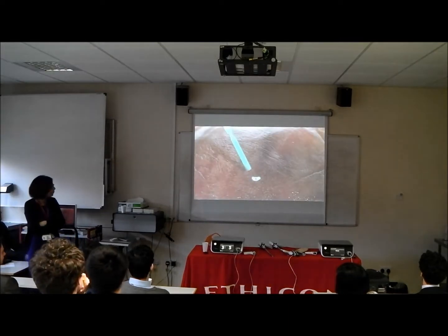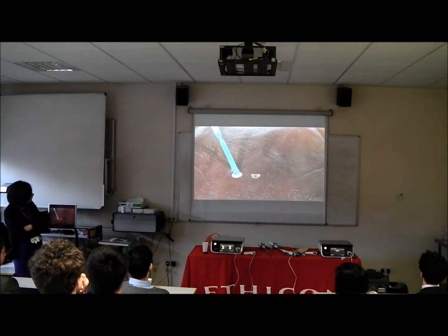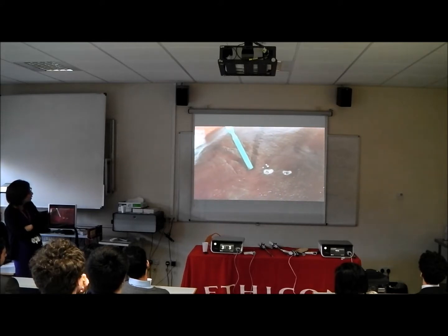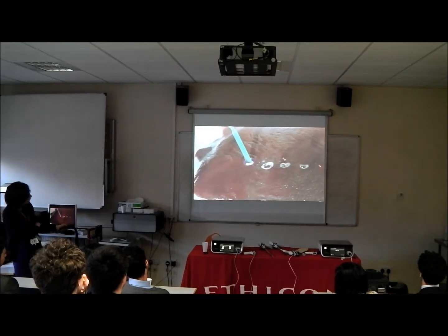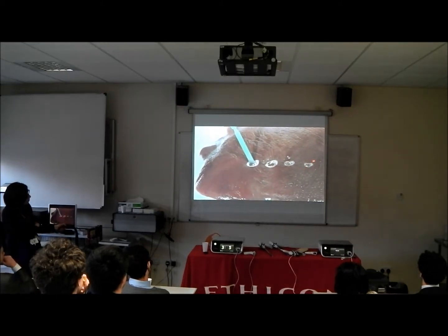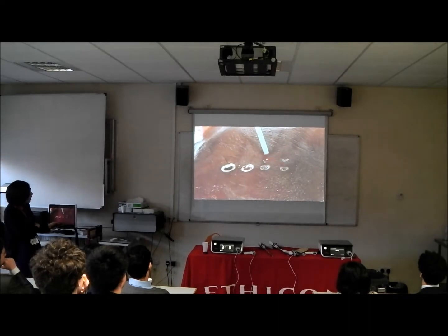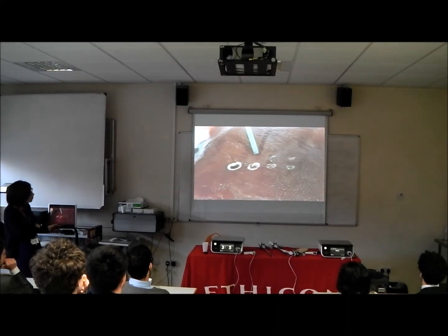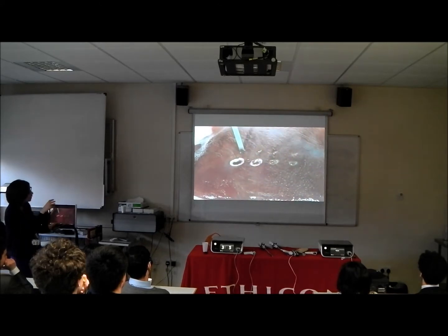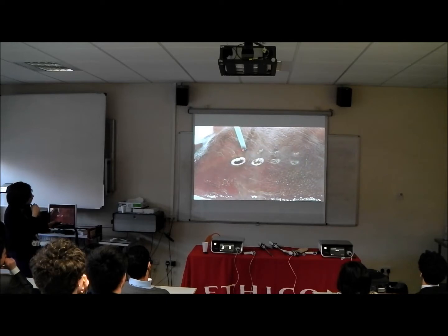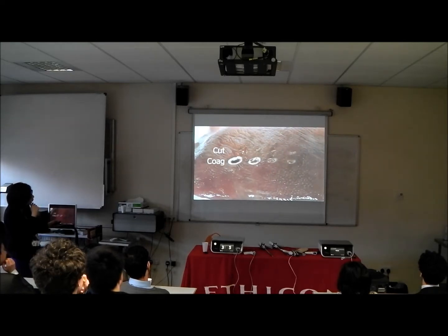Liver. So you see, now the surgeon is trying to coagulate. So what he's trying to do is he's using it for longer periods of time and trying to show you that if you use it for shorter periods of time, the spread is less. The longer you use it, the spread is more. Is that clear? Yeah? So now here they're using the cut current. So high frequency, rapid spurts of electric current coming, and you can see that the tissue has literally evaporated, so you can produce a cut effect.